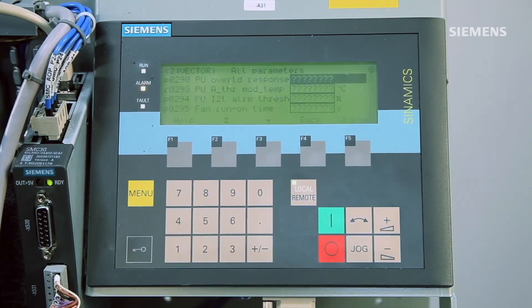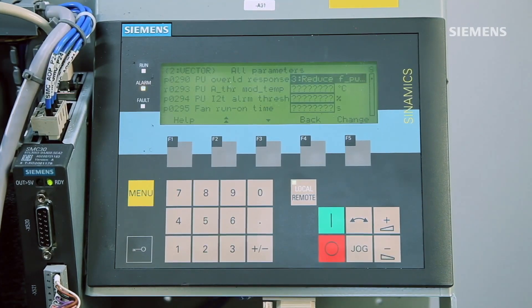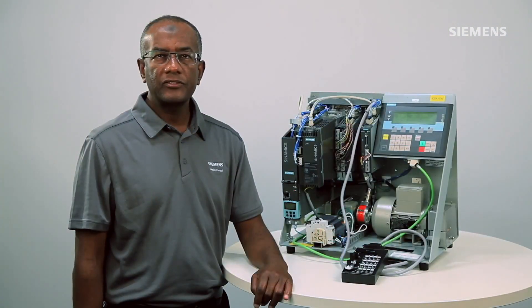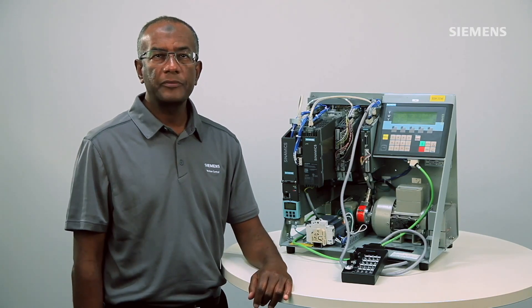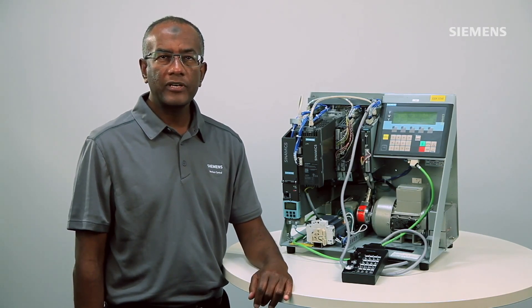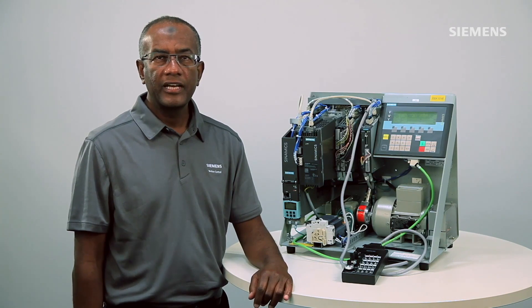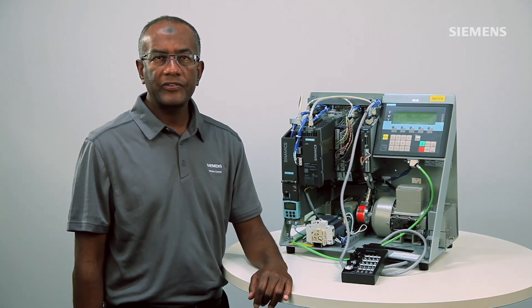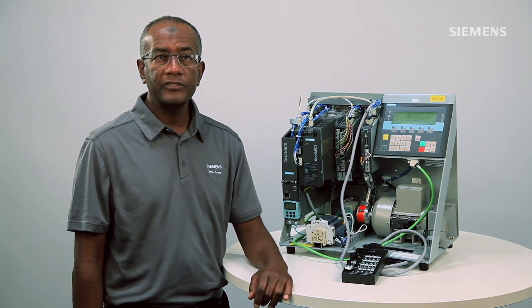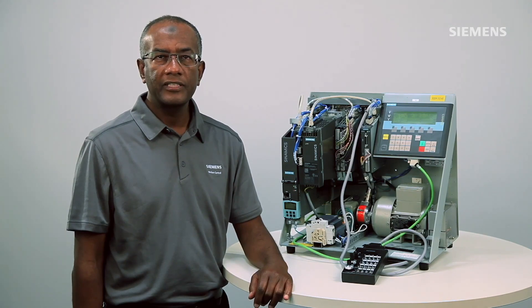Notice the display shows PU overload response. The power unit overload response or parameter 290 allows us to set the drive to respond with multiple preventive actions before an overload fault occurs. This parameter gives us different tactics to aid in avoiding the fault entirely and thus it maintains consistent uptime.